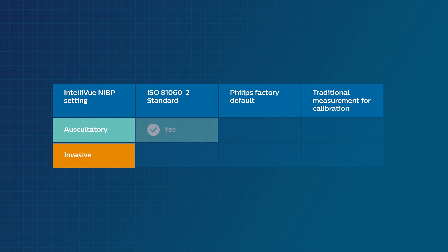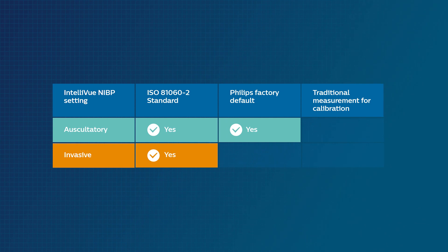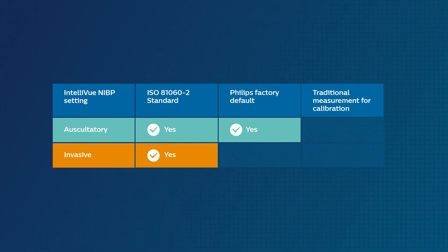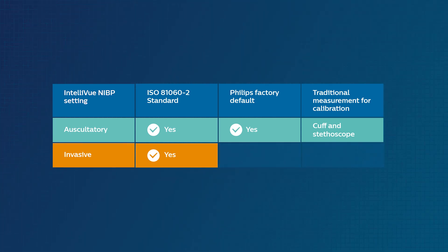Both algorithms conform to the ISO 81060-2 standard and correspond to a traditional method of measuring blood pressure. The auscultatory setting is the factory default for IntelliVue monitors and provides NIBP values that approximate to manual cuff and stethoscope readings. The invasive setting provides NIBP values that approximate to values measured using the intra-arterial method.